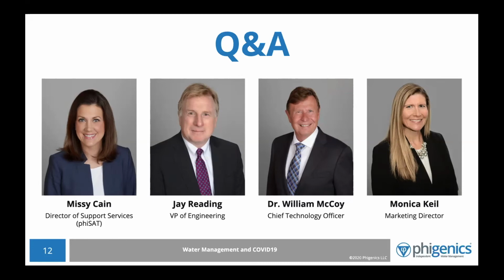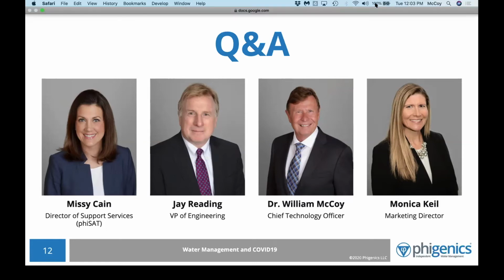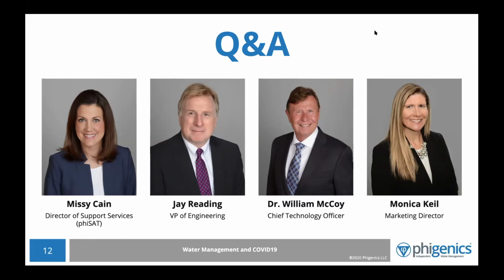The key perspective is to consider how the safety of the environment is being assessed and determined. In a negative pressure room, air quality testing is typically performed to ensure the air is safe for patients, along with confirmation of air exchanges based on the definitions of negative pressure in a healthcare facility. The connection to water is direct: the same criteria and steps taken to ensure air safety should be applied, via a checklist or process, to ensure water safety as well.